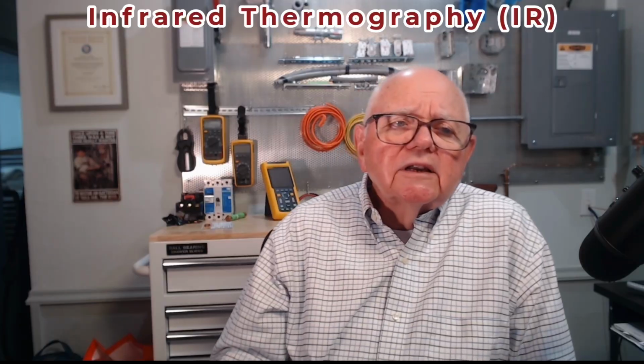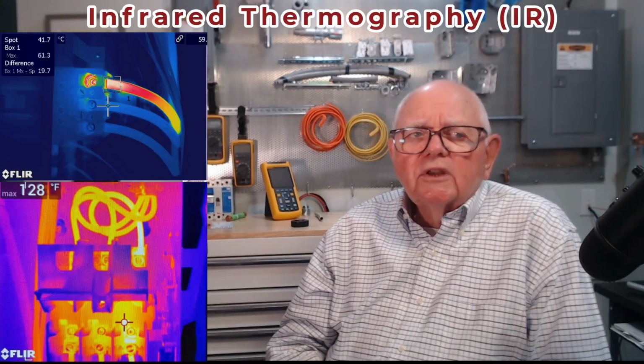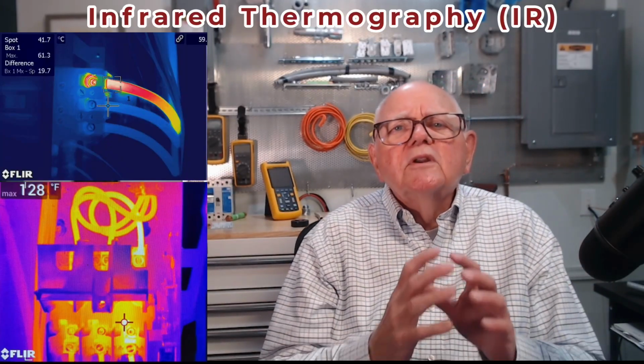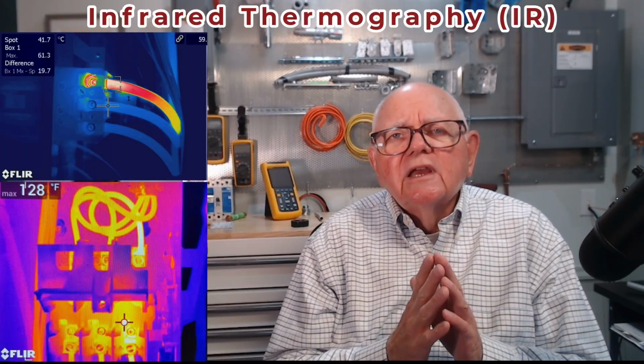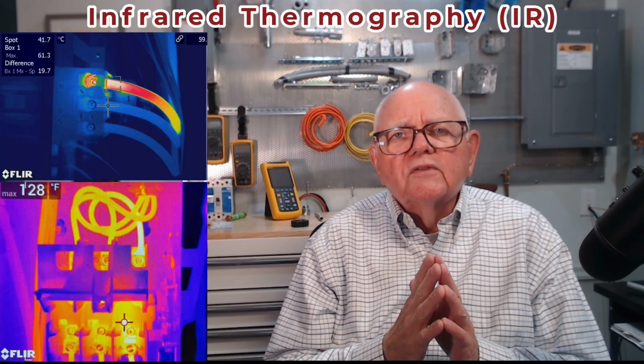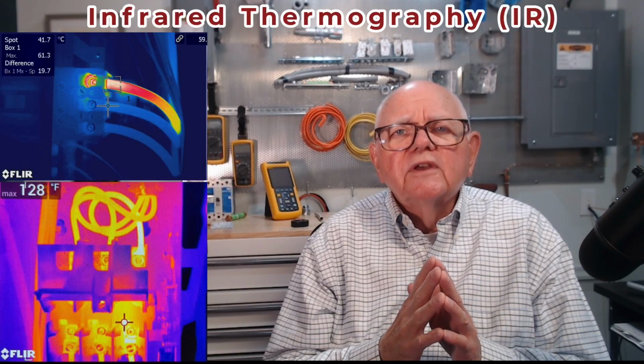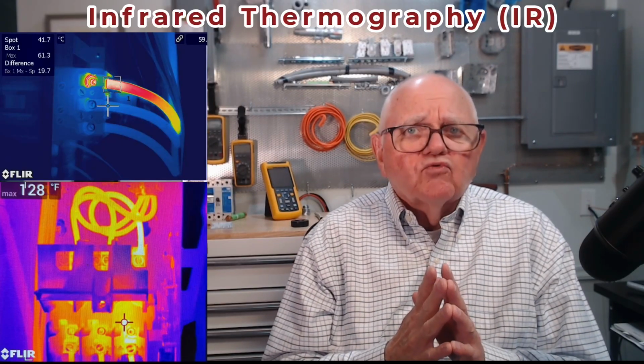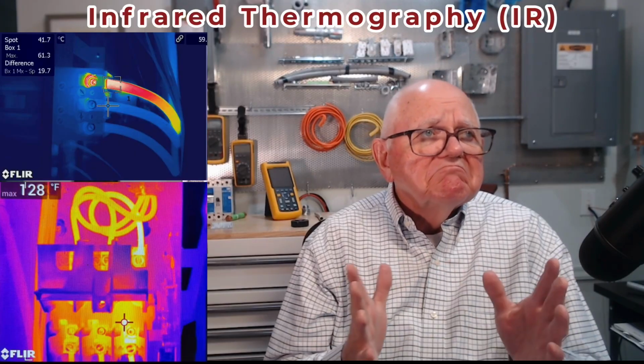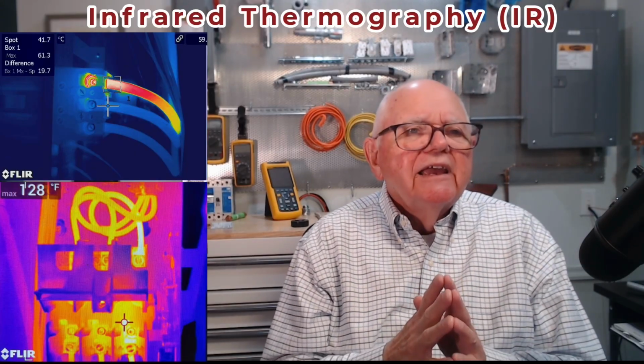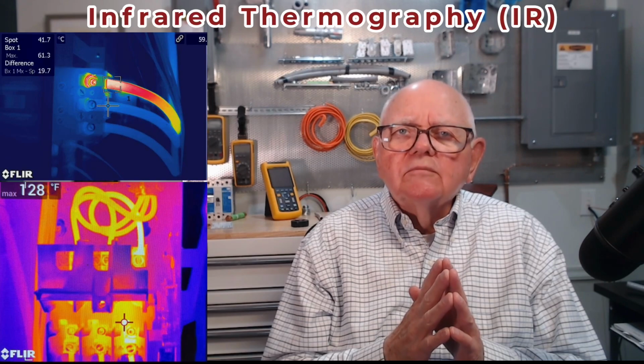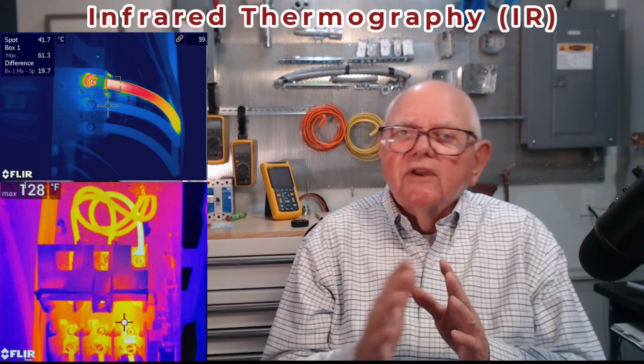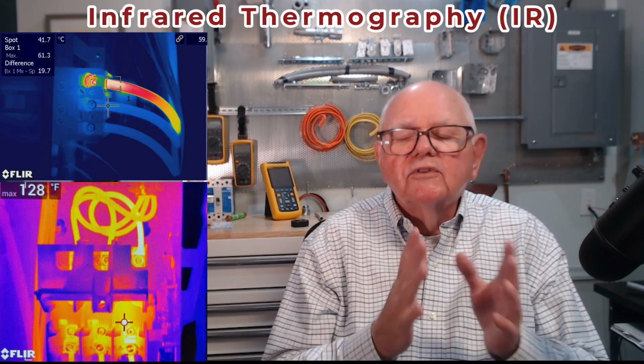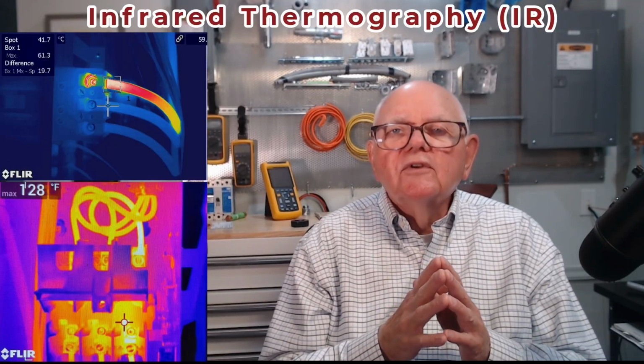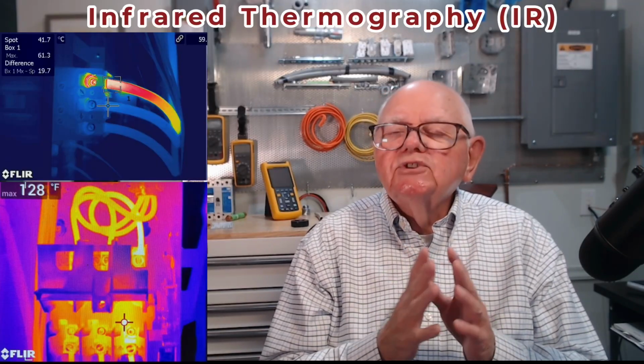Finally, let's talk about infrared thermography. Let's take a look at a couple of infrared thermography pictures. When we look at infrared thermography pictures, as I said, what we're looking at on these images is the difference in temperature between 2 points. You may look at an infrared thermography image and go, whoa, that looks really hot. It's red. And the other one is dark blue, or whatever it is, right? And that's not what's really important. In your software, you can hover over different points within those images and read the difference in temperature values. That's what you're concerned about.